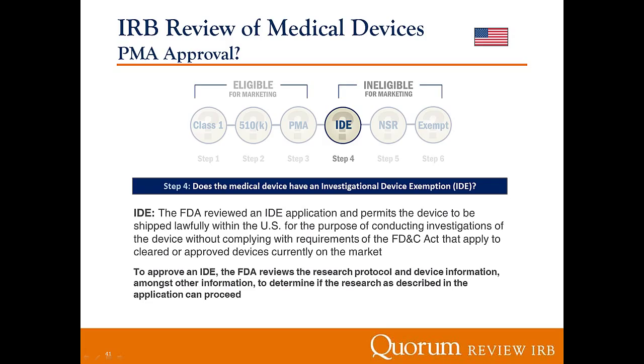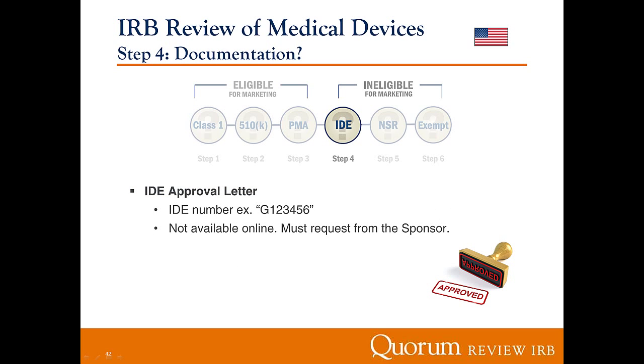So if a device has an IDE, what documentation does the IRB actually have to receive to feel confident that it knows the FDA has issued this IDE? Well, there's the IDE approval letter. This letter is proprietary, so it's not going to be online. It's not available anywhere. The only way that the IRB can receive the letter is from the sponsor itself. So the sponsor will have this letter, and that letter will indicate what the IDE number is for the device. It starts with a G, has six numbers after it. Again, you must request this letter from the sponsor. Only with that letter will you know that the device does have an IDE, so it's okay to use that device in the clinical trial.